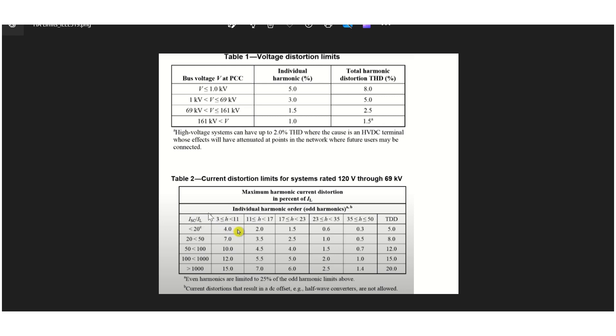The key parameter here is the ISC/IL ratio — the ratio of short circuit current to load current. If the ratio is less than 20, the first row applies and the harmonic content must be limited to 4%. If the ratio is greater than 20 but less than 50, up to 7% current harmonic distortion is allowed.